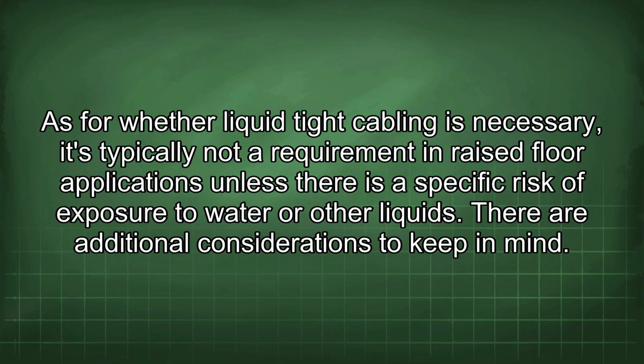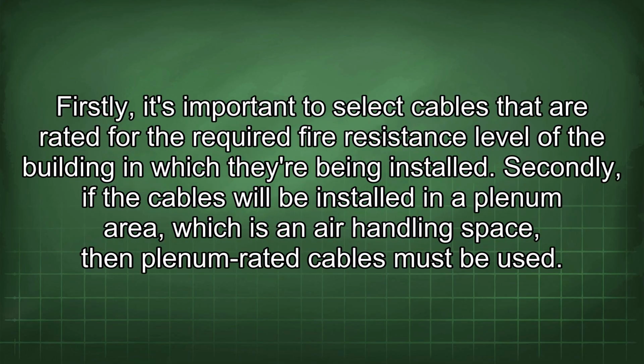As for whether liquid-tight cabling is necessary, it's typically not a requirement in raised floor applications unless there is a specific risk of exposure to water or other liquids. There are additional considerations to keep in mind. Firstly, it's important to select cables that are rated for the required fire resistance level of the building in which they are being installed. Secondly, if the cables will be installed in a plenum area, which is an air handling space, then plenum-rated cables must be used.